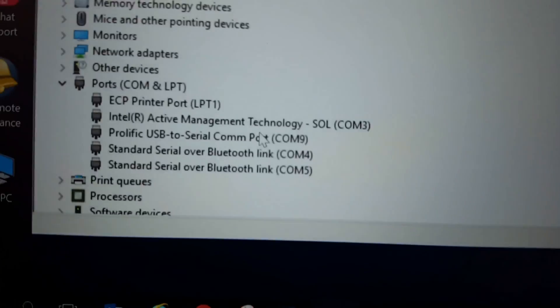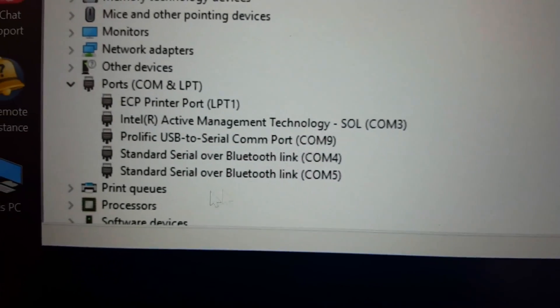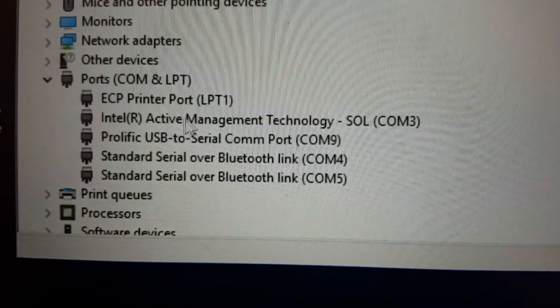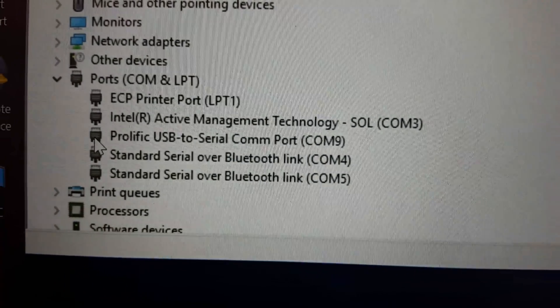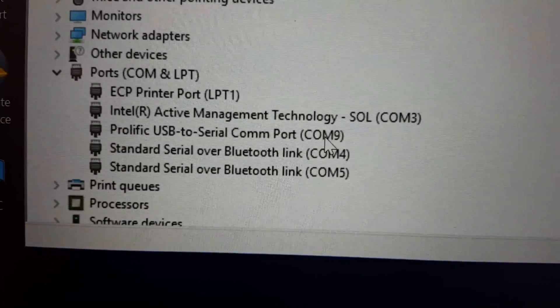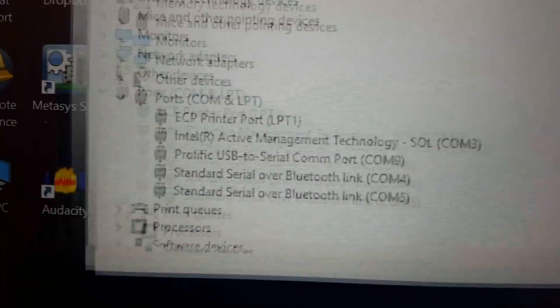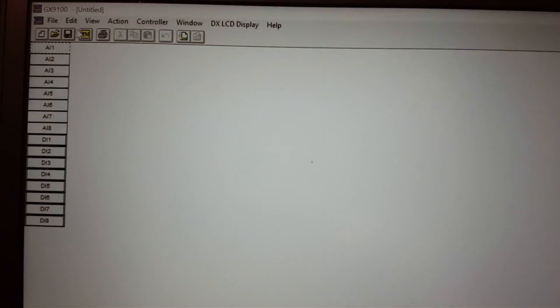You can see here I plug it into a USB port just like that, and then it will populate right there in Device Manager. Pay close attention to the COM port that it comes in on — it came in on COM port 9 on my particular machine. Now that is going to create an issue with HVAC Pro as well as the GX9100 software.